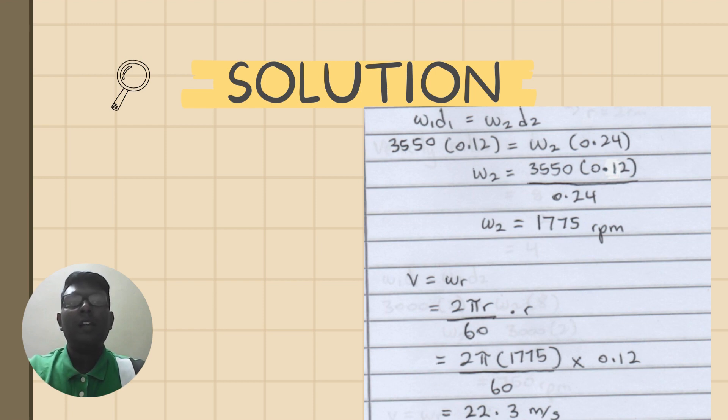Place all the values into the formula and you will get the speed operation of the compressor with the value of 1775 rpm. Then we will be searching for the velocity of the belt with the formula of the speed rate...